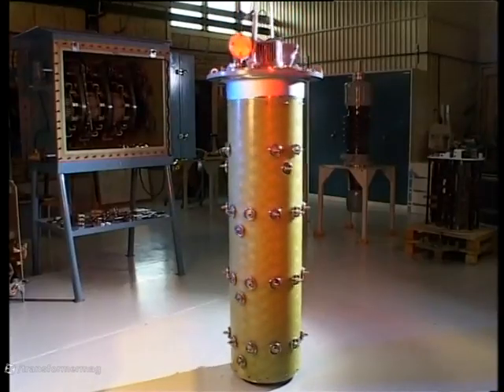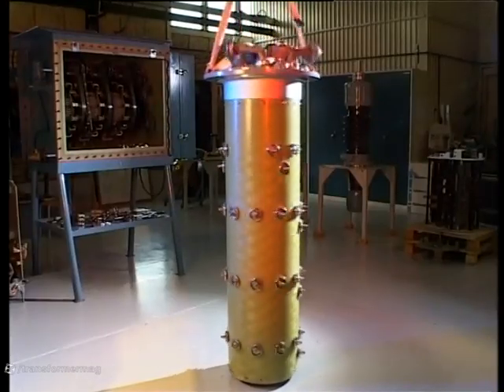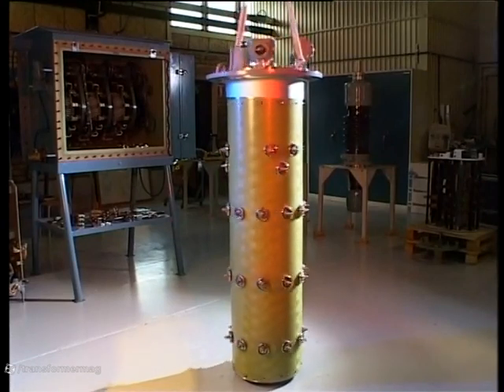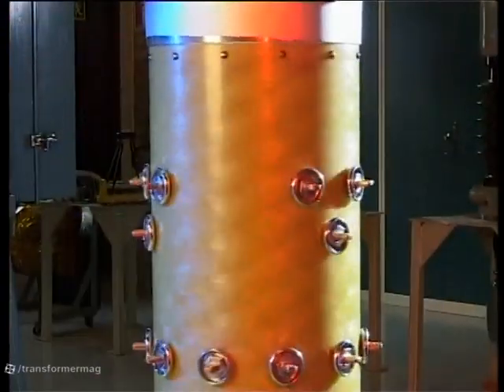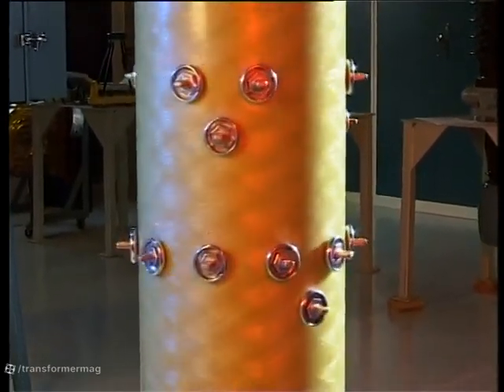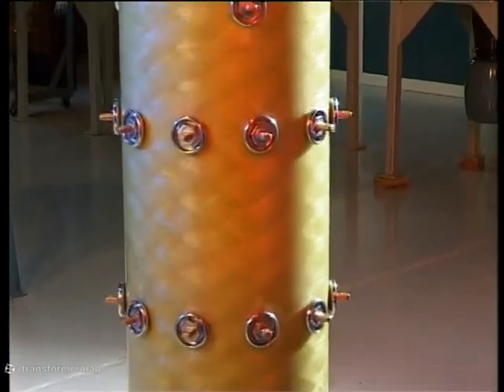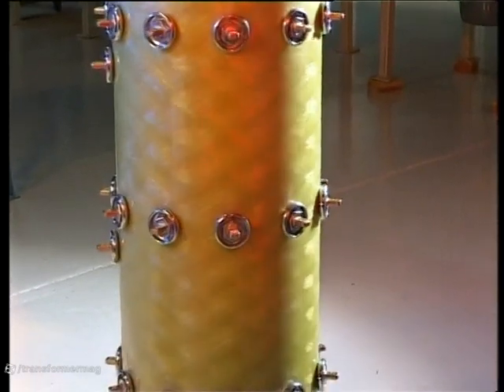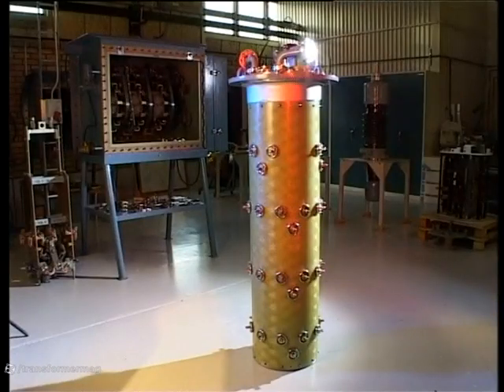An on-load tap changer could be called the gearbox of a transformer. Its job is to switch turns of a transformer's regulating winding in and out to give a uniform voltage on the outgoing line. The on-load tap changer can adjust the transformer without interrupting the power. In this maintenance guide, we'll be dealing with on-load tap changer UBB. It contains a rotating insert which switches between the different contacts.